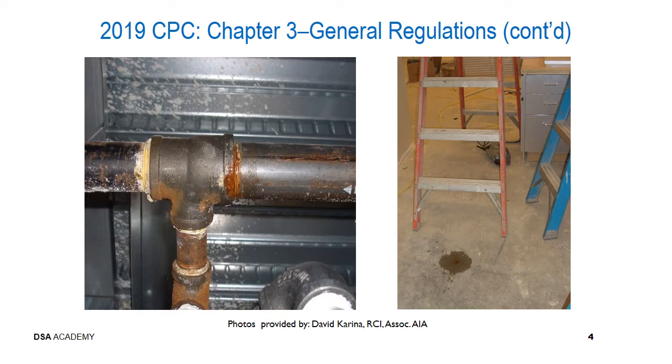You can rest assured that with a 200 psi test for 2 hours, there are no leaks that are going to survive that. That's the whole intent of that type of test. It's going to identify any leak. Unfortunately, looking at the image on the left, I don't see any Grinnell fittings. I don't see any Gruvlok fittings. So depending on what the impact to the right side of that fitting is, this could be a very involved repair process for the plumbing contractor.